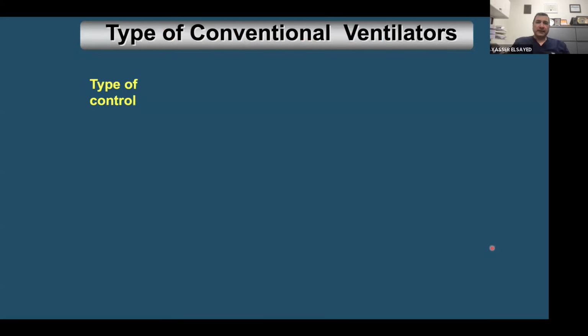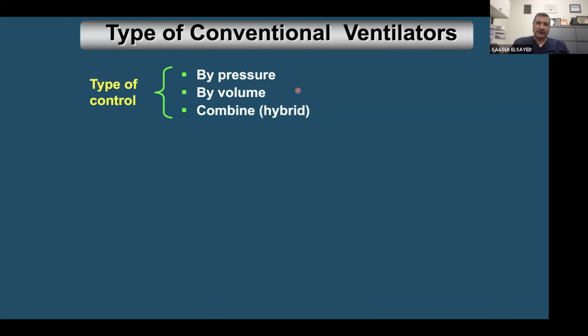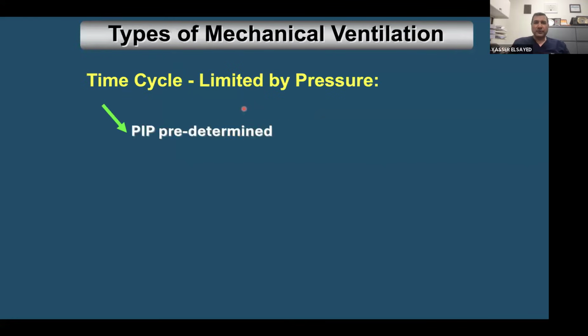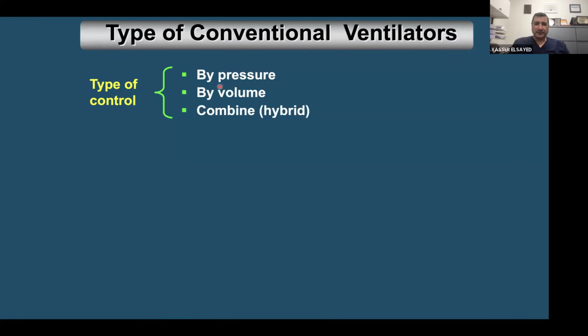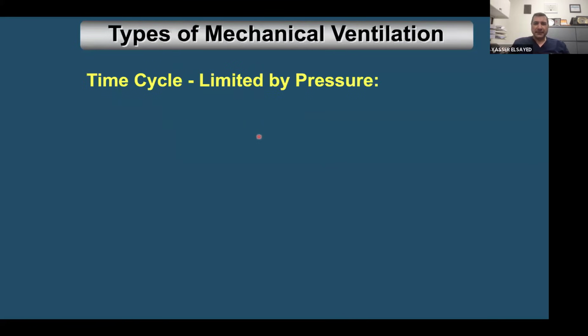Now we'll talk about the types of conventional ventilators. We have the type of control, either pressure or volume, but it can be combined or hybrid. The one that we are using in most of our units, and I assume you are using the same model as our machine, is pressure, but hybrid with volume. And we'll explain how it works. Again, we are focusing on the pressure limited. Just ignore the volume for now because we are not using it. We are using the hybrid mode, but just focus now on the time cycle limited by pressure. Simply, it is PIP predetermined. So we predetermine a PIP of 20, 25, or 30 without volume. We're not talking about hybrid volume now.